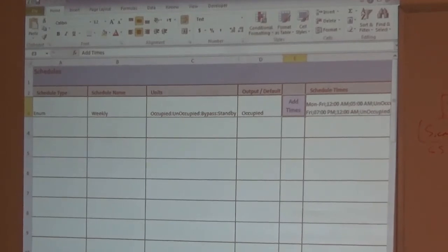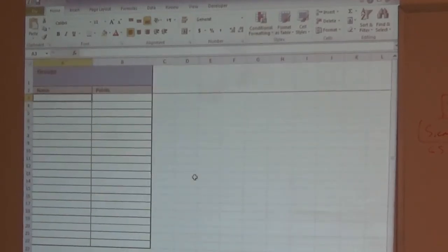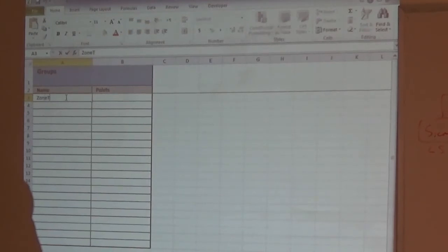My last option, if I want to take advantage of it, is groups. A group is a concept where, let's say I want to take a look at all zone temperatures and put them into one bucket. So I take the zone temperatures for all my rooftops or VAV boxes, give the group a folder name, like zone temp. Our point naming convention is ZN-T for zone temp, so it'll pick any points with ZN-T in them and put them into this bucket. Or like VAV flows.